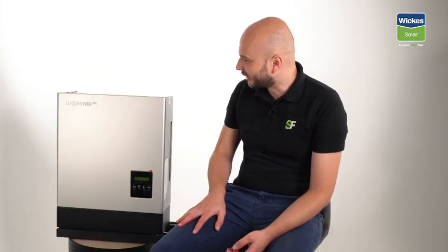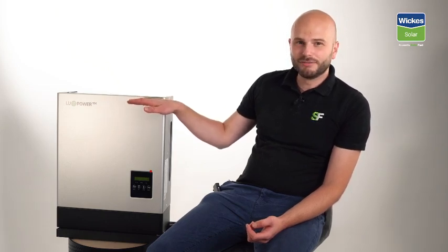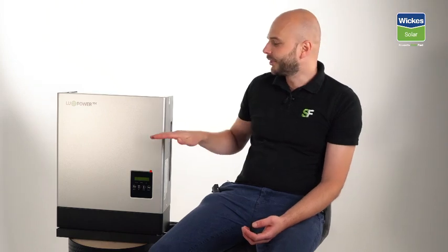So this beast I've got with me here is a hybrid inverter. It's a Lux hybrid inverter. Now, hybrid inverters are called that name because there's 2 devices in one. So in a nutshell, they're designed to connect with batteries and with panels. So you can start storing your electricity and using it when you need it. Now, they're a lot bigger because they've got a device for inverting the electricity from your panels into AC for your house, as well as another device called a DC to DC converter for taking the higher voltage from the panels and converting it into a lower voltage to charge your batteries.